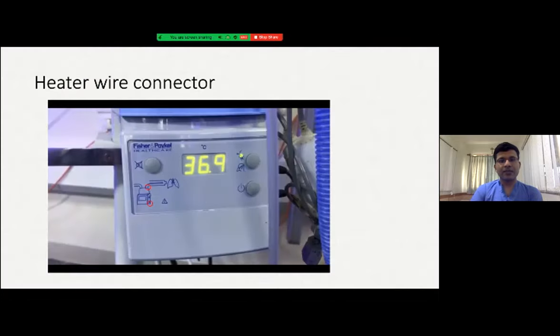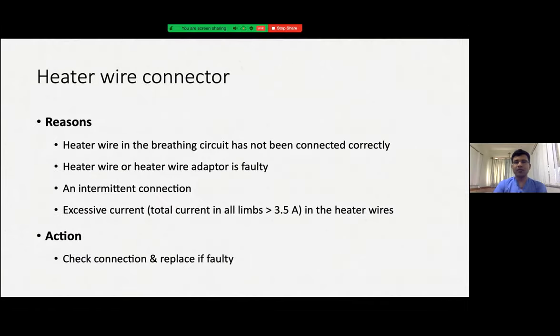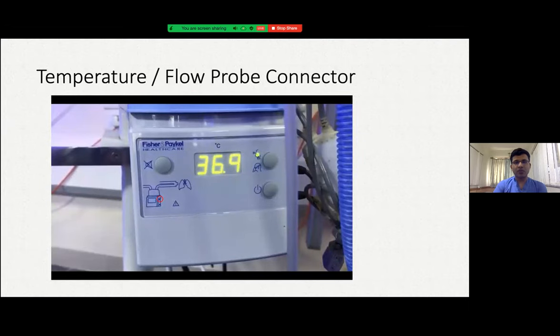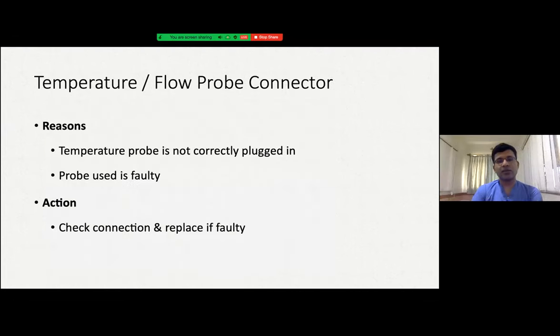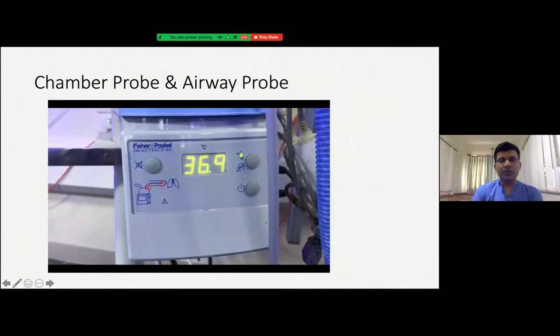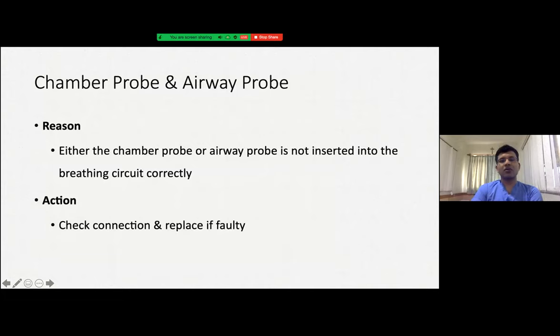The heater wire connector alarm occurs when the heater wire is not connected properly, is faulty, or there is a problem with current flow. Check the connection; if connections are fine and the alarm persists, replace the connector — hand it to the biomedical team for replacement. If there is a problem with the temperature or flow probe connector, this alarm will activate. Check whether it is faulty or improperly connected; if properly connected it means it is faulty and must be replaced. There can also be alarms for the chamber probe and airway probe together, occurring when either is dysfunctional or not properly inserted — replace the temperature sensors.